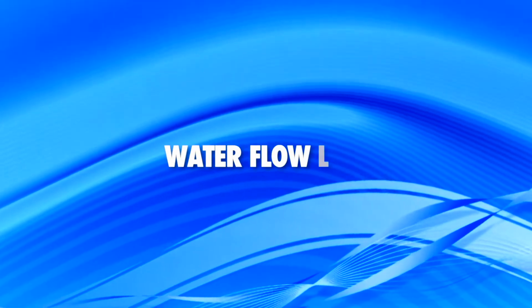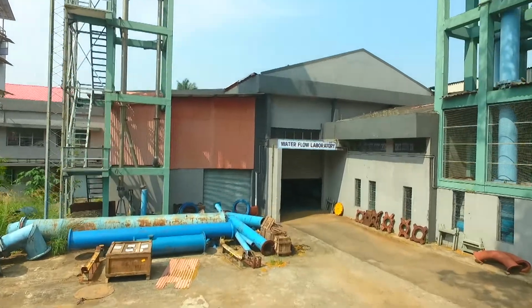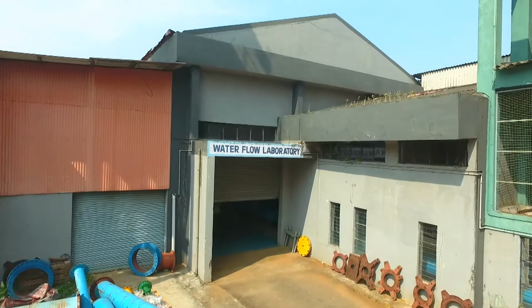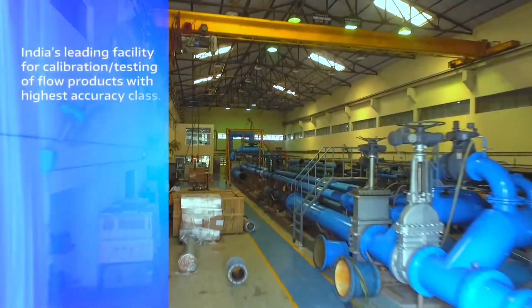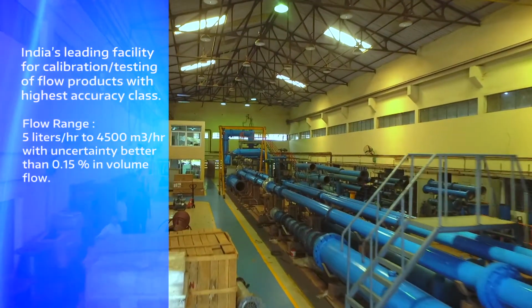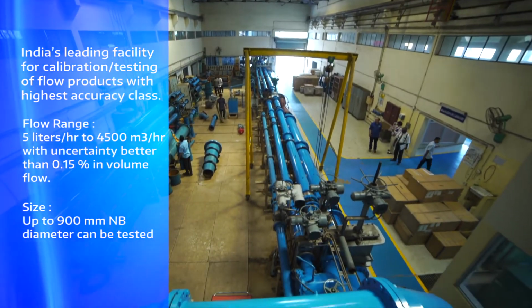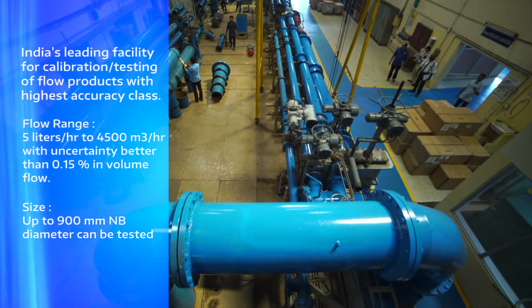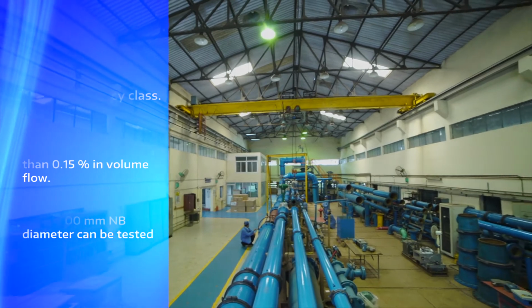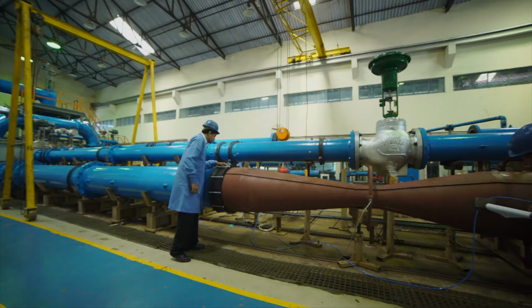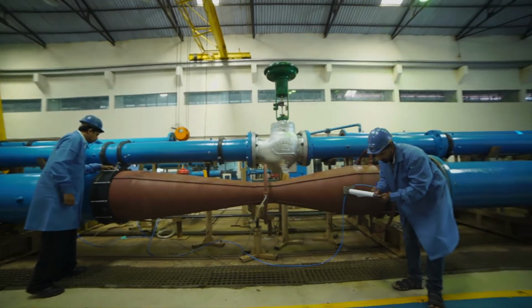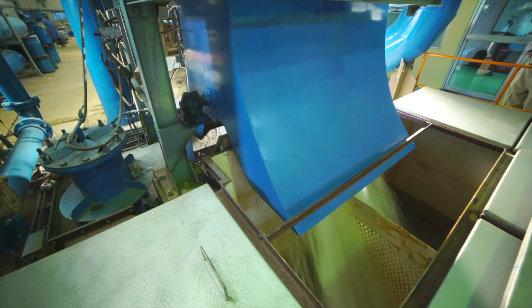The Water Flow Lab is India's leading facility for evaluation of flow products with the highest accuracy class. It can handle flow range from 5 liters per hour to 4,500 cubic meters per hour, with uncertainty better than 0.03% for mass flow and 0.05% in volume flow.